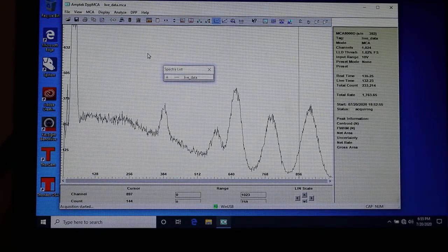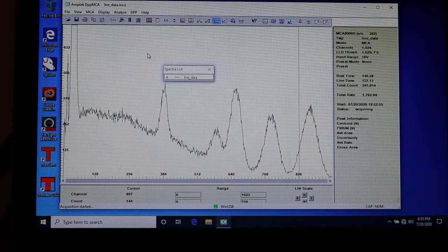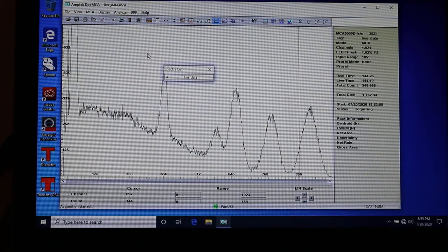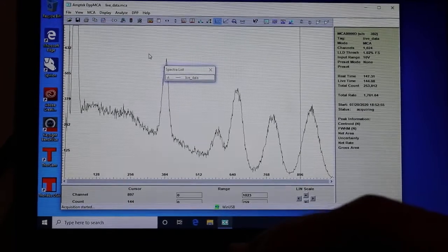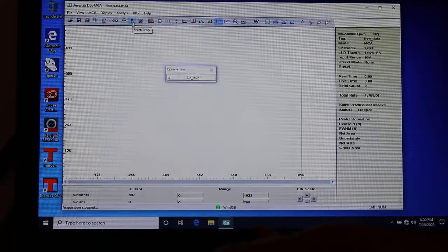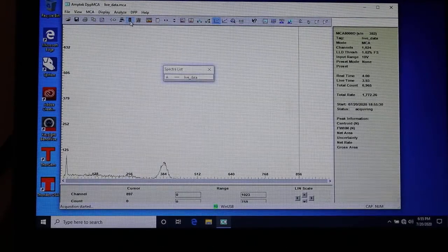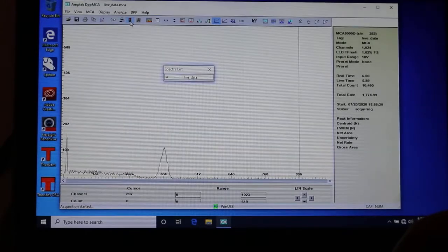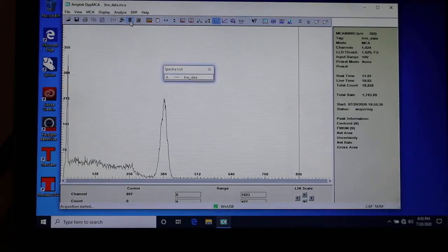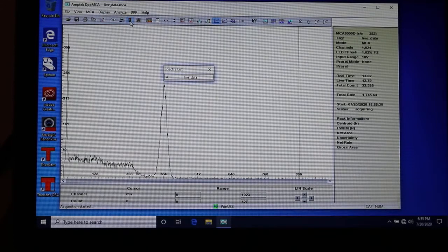So the point for telling you this is that by changing the amplifier knobs, I've changed the overall level of all the voltages going into the MCA. I'm making them smaller or bigger, and if I clear it here, I can compress the whole cesium-137 spectrum from taking up the whole screen to taking up just a little bit over there. You'll see the same spectrum that we started with, the one that was running for a while, but now it's all compressed in this third of the screen. Let me tell you why this is important and what we're going to do.